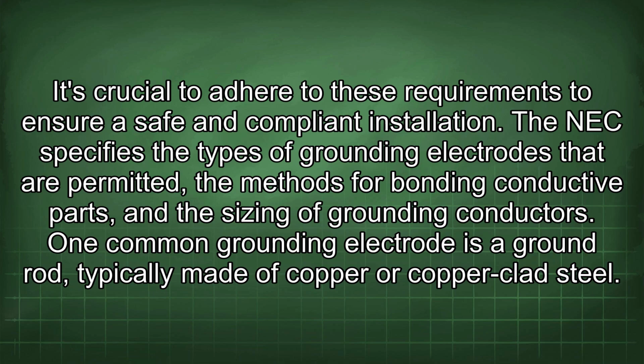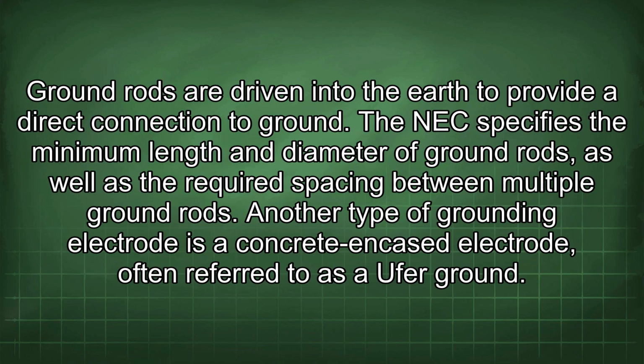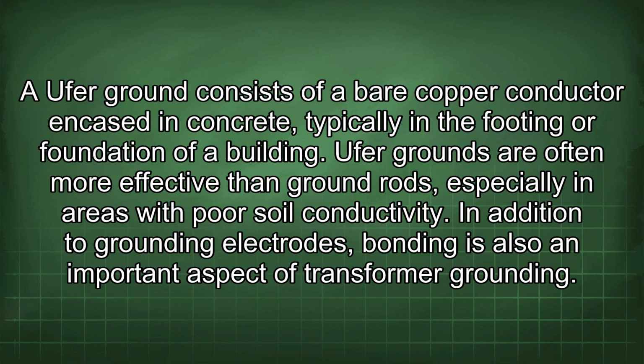The NEC specifies the types of grounding electrodes that are permitted, the methods for bonding conductive parts, and the sizing of grounding conductors. One common grounding electrode is a ground rod, typically made of copper or copper-clad steel. Ground rods are driven into the earth to provide a direct connection to ground. The NEC specifies the minimum length and diameter of ground rods, as well as the required spacing between multiple ground rods. Another type of grounding electrode is a concrete-encased electrode, often referred to as a UFER ground. A UFER ground consists of a bare copper conductor encased in concrete, typically in the footing or foundation of a building. UFER grounds are often more effective than ground rods, especially in areas with poor soil conductivity.